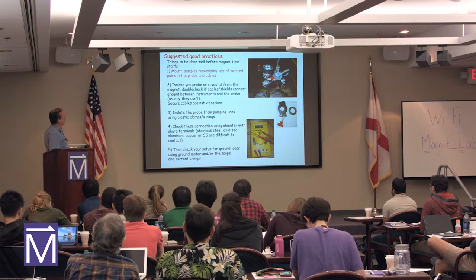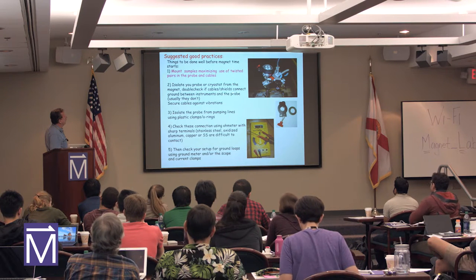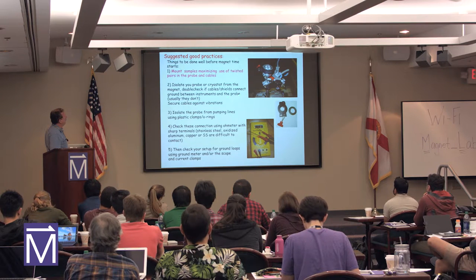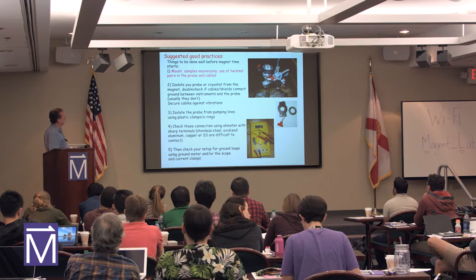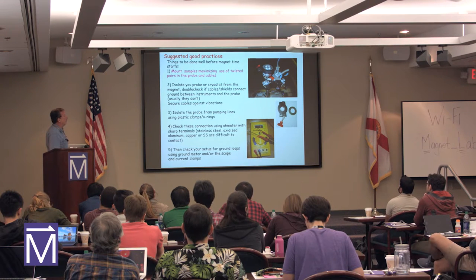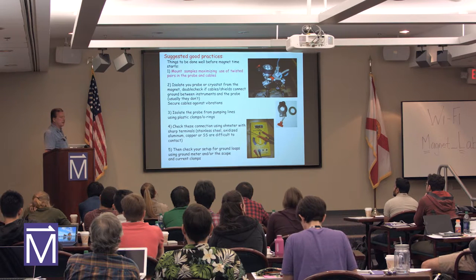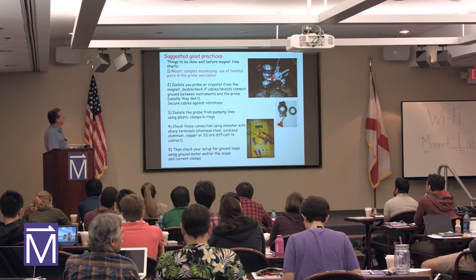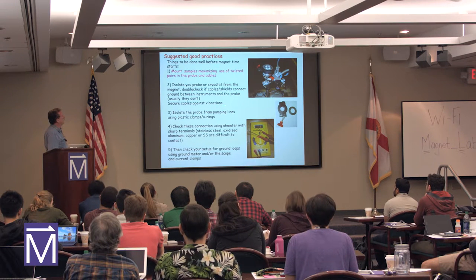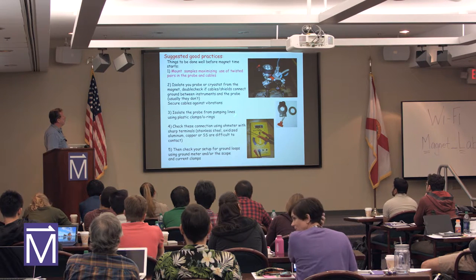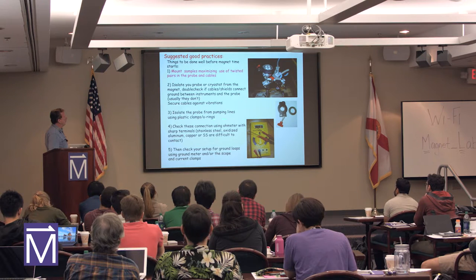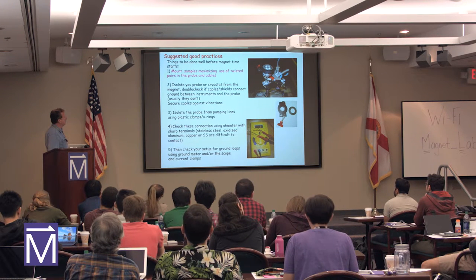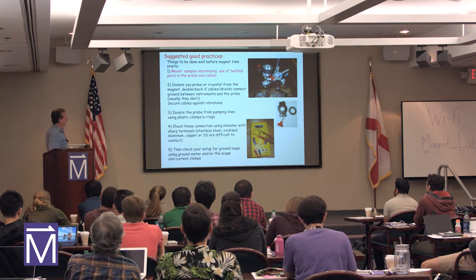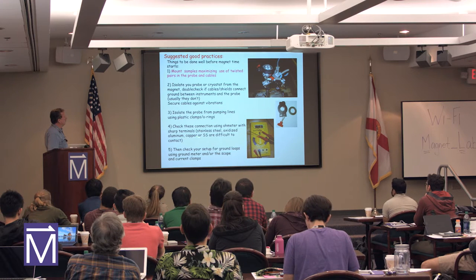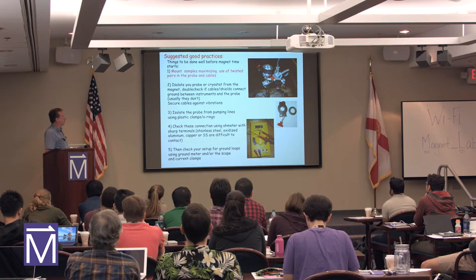Then isolate your probe or cryostat from the magnet. Double check if cables and shields connect ground between instrument and the probe. Usually they don't. Secure cables against vibrations. This is what Matt mentioned. And vibrations in our lab are higher because we have hundreds of gallons of water running through the magnet, which doesn't occur in a superconducting magnet. Isolate the probe from pumping lines using plastic clamps and O-rings like this. Check this connection using an ohmmeter with sharp terminals, because stainless steel, oxidized aluminum, and copper are sometimes difficult to contact with terminals that are not sharp.